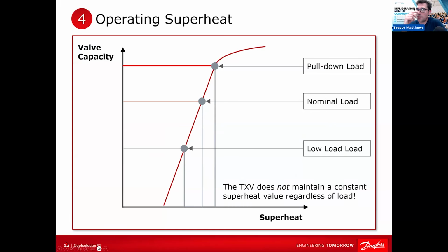Want to dive into operating superheat a little bit? Yeah, okay. So the thing about the sensing bulb, the charge in the sensing bulb, is it's not just refrigerant. And so just like how we had glide in refrigerants, you can mix and match the components, the gases, whatever you want to call it, in the sensing bulb to work on the profile of opening and closing. Do you want it to open with very little superheat at low temp? Do you want to open slow, close fast? All of these things can be done.